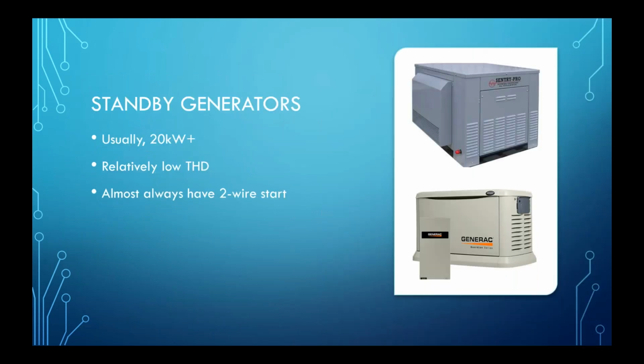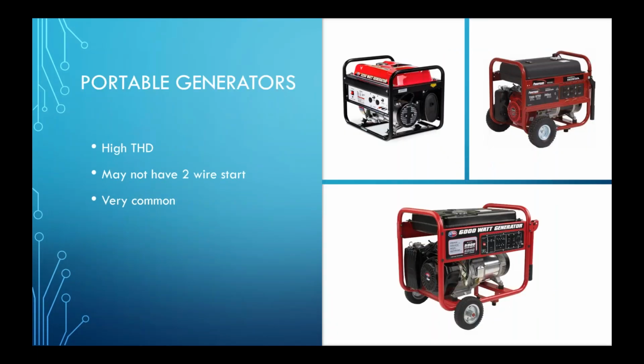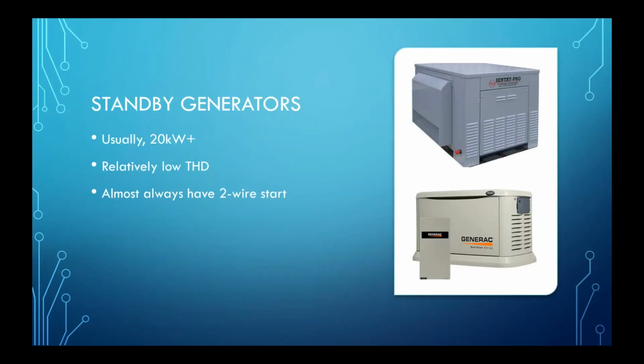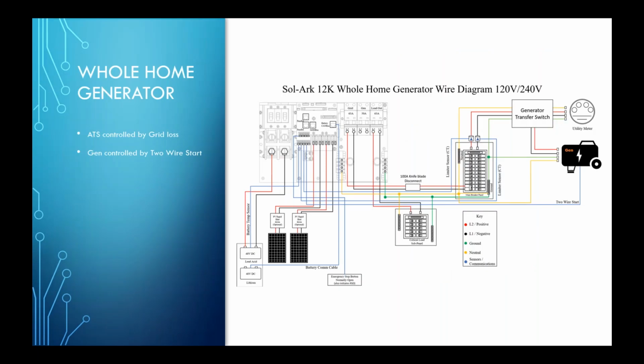The bigger guys, the whole home backup generators, 10 kilowatts, 15 kilowatts, 20 kilowatts, etc. These are going to be the Sentry Pros, the Generacs, the Briggs & Stratton, the Kohlers. They will have a 2-wire start. Depending on which manufacturer, it's either included or maybe it's an accessory. Either way, there's going to be a 2-wire start available. Again, that's how the Sol-Ark is going to start these guys, is the 2-wire start kit. But having said that, whether you have the little ones or the big ones, 208 volt, 240 volt, the Sol-Ark can handle it. So this is a wiring diagram that has an example of a whole home generator.